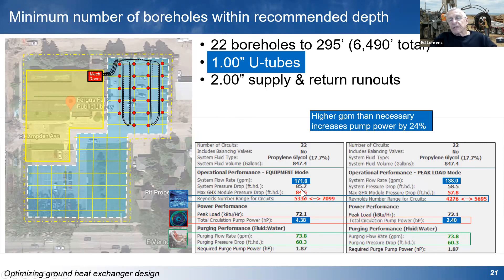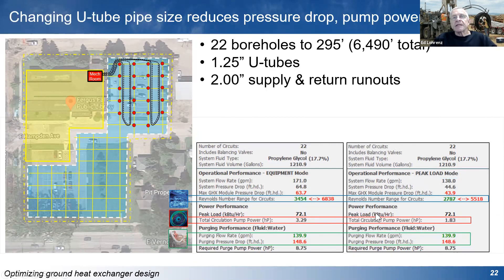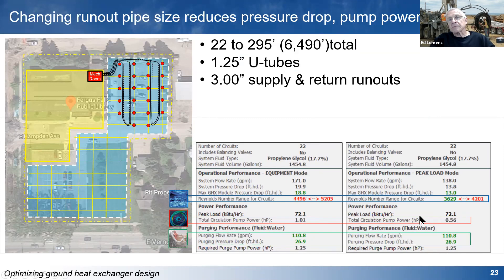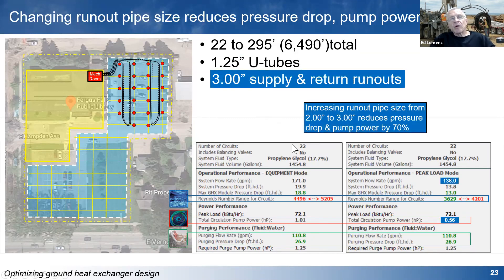This analysis was based on equipment design loads; the block load version uses 138 GPM, making a pretty big difference in pump sizing. You should be aiming for block loads of the building, maybe giving yourself a little safety factor and allowing for a variable speed pump. The next option: changing to one-and-a-quarter-inch pipe instead of one-inch decreases the pressure drop. We're down to 3.3 horsepower at 171 GPM, or down to about 44 feet of head and under two horsepower if going with the block loads.